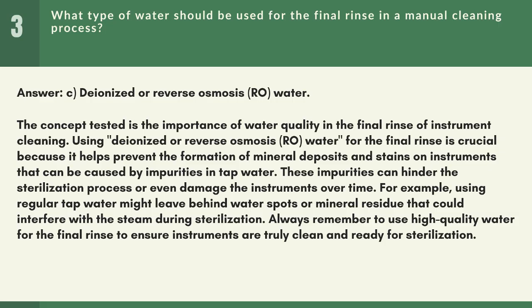The concept tested is the importance of water quality in the final rinse of instrument cleaning. Using deionized or reverse osmosis, RO, water for the final rinse is crucial because it helps prevent the formation of mineral deposits and stains on instruments that can be caused by impurities in tap water. These impurities can hinder the sterilization process or even damage the instruments over time.